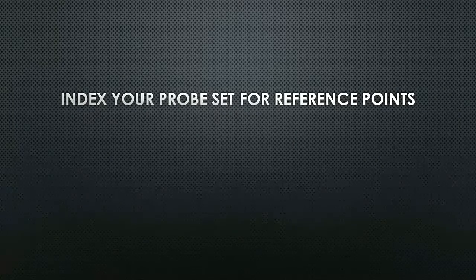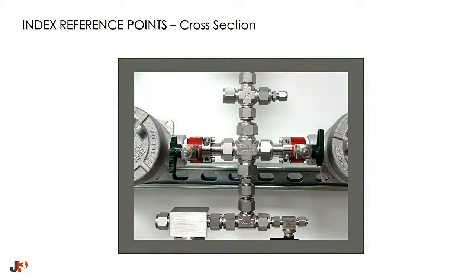Indexing your probe set for reference points. Note the way that the probe set is currently aligned. For best results, you should physically mark the probe set to ensure that you can restore its original alignment after cleaning. On one side of the probe set, locate the slot that's located just inside the red section. Please note that the slot might not start out perfectly centered. That's okay. This will be your first reference point.